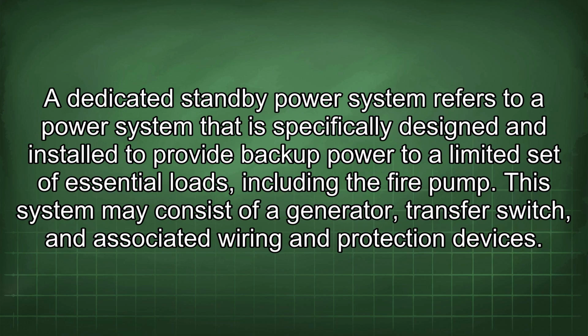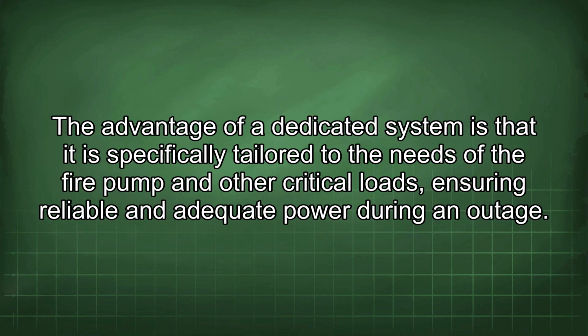A dedicated standby power system refers to a power system that is specifically designed and installed to provide backup power to a limited set of essential loads, including the fire pump. This system may consist of a generator, transfer switch, and associated wiring and protection devices. The advantage of a dedicated system is that it is specifically tailored to the needs of the fire pump and other critical loads, ensuring reliable and adequate power during an outage.